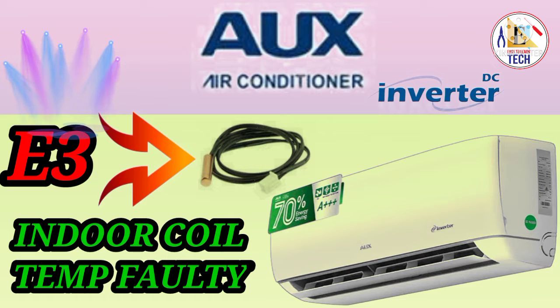First of all, you have to check the placement, then check the connection in the PCB. If the placement and connection are good, then you have to check the resistance of your coil sensor. If the resistance is not good, then you have to change the sensor and start the unit. If you get the solution by doing this, then you can stop the process and make your unit work.